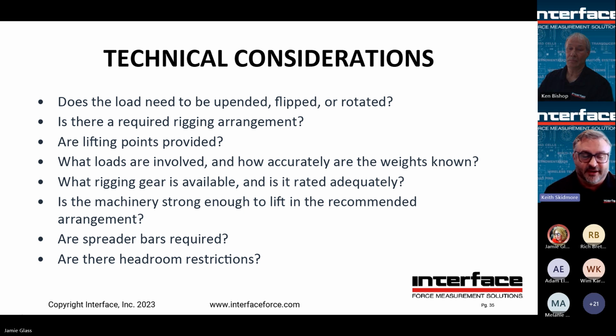Again, spreader bars and things may be required, and those would be just, say, to spread the load appropriately on a sling so that you're not overly loading a single point. Again, headroom restrictions. We have a number of customers who have to move things around, and you really don't have room to get a crane in. So you're moving a large load frame into a lab, for example. There may not be room to come in with a crane, so you might have to rig something. Sometimes you even have to modify the roof or the ceiling, come in with a crane through the ceiling. So things like that are worth considering.